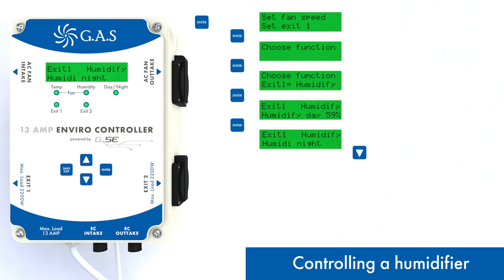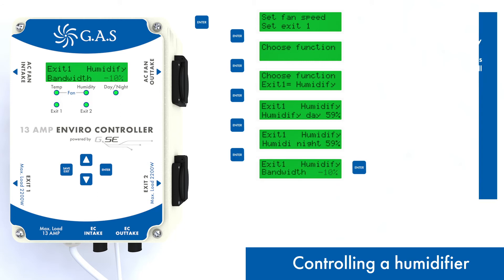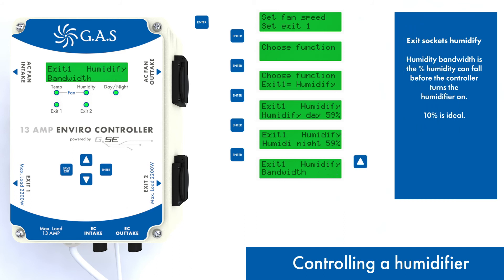Make sure the Humidify setting is below the humidity value you set for your fans. Bandwidth is the percentage the humidity can drop before the controller will turn the humidifier on. A 10% bandwidth is advised.